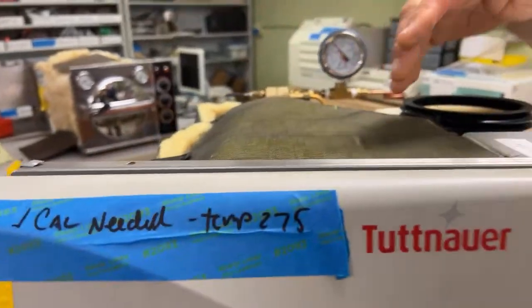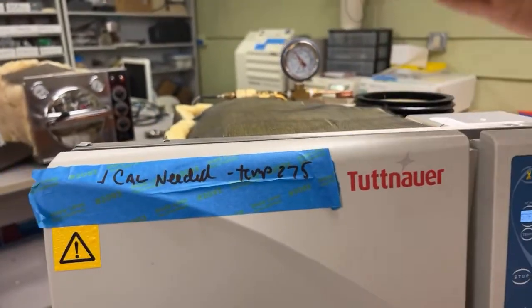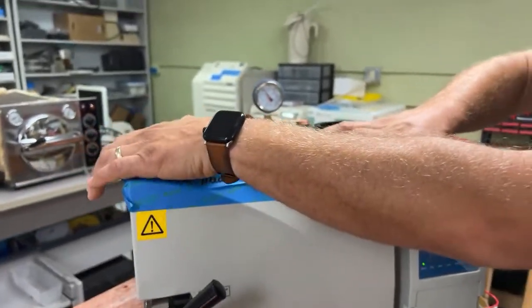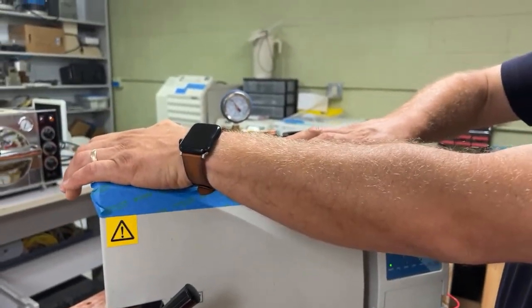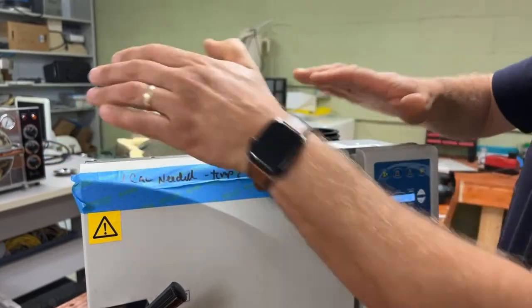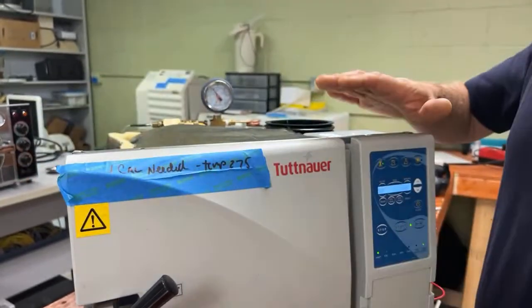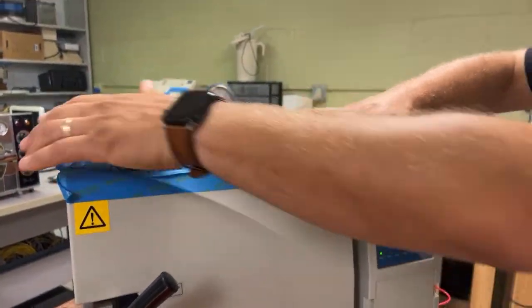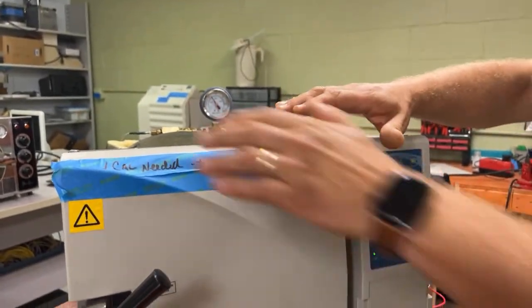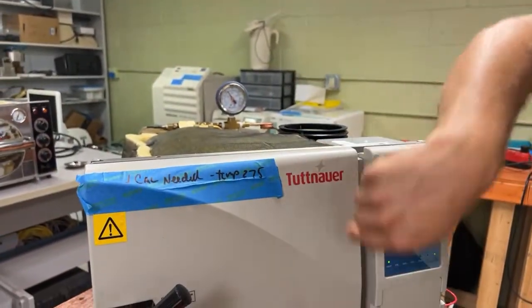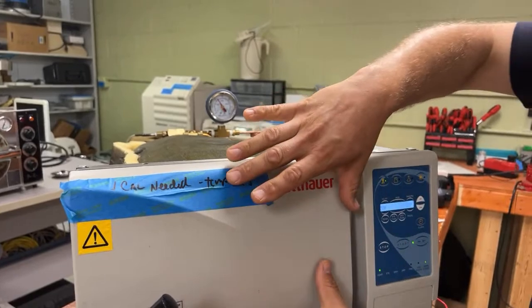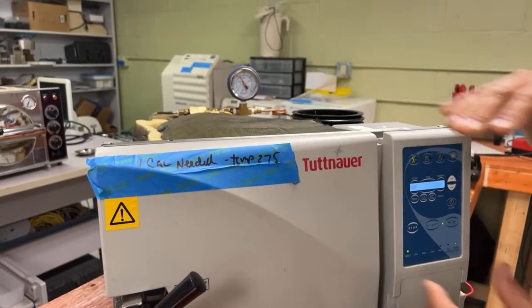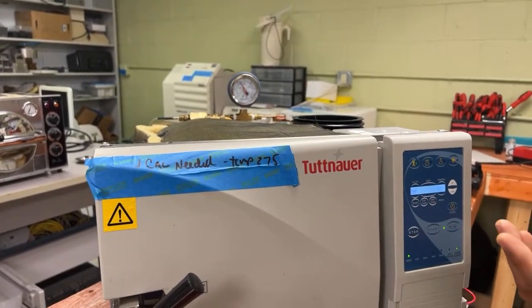Specifically up here in the front of an autoclave, when you're running an autoclave, you should be able to hold your hands on both sides of the door, and you should be able to hold them there. If you ever can't hold your hand on the sides of the door, then what that tells me is that the gasket in the middle on the door is leaking, and that's something that should be replaced periodically.